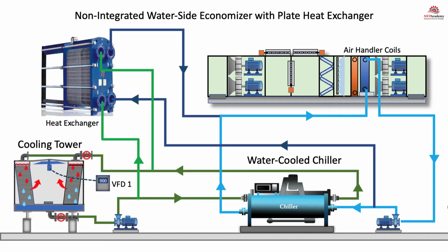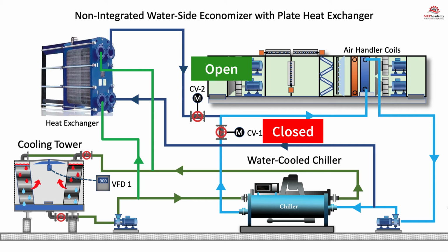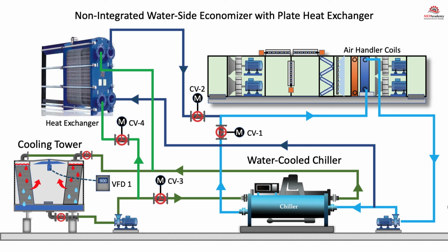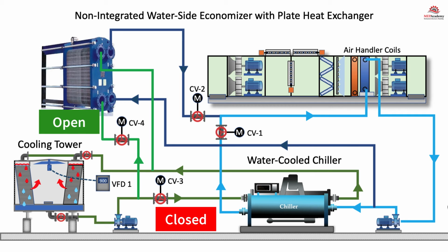Control valves CV1 and CV2 will be installed on the chilled water side of the economizer, so that when the economizer is activated and the chiller shuts off, CV1 will close and CV2 will open. This allows the water from the air handler or building load to bypass the chiller and go directly to the heat exchanger. Next, there will need to be control valves on the condenser water side of the heat exchanger to bypass the chiller. Control valves CV3 and CV4 are installed on the condenser water supply to the chiller and the inlet piping to the heat exchanger. During waterside economizer mode, CV3 will close, preventing water from entering the chiller, and CV4 will open, allowing the flow to be diverted from the chiller's condenser to the heat exchanger.